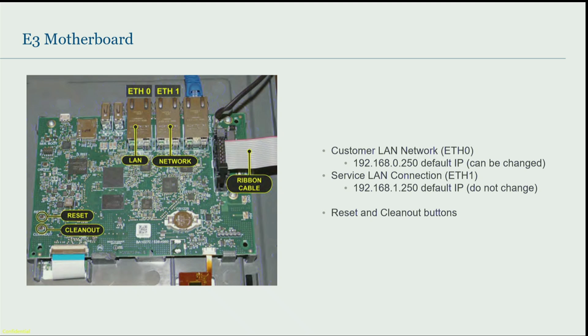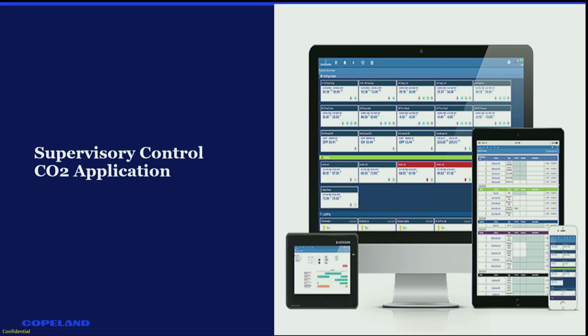So let's talk about communication protocols for CO2 specific devices. When we talk about the CO2 system and how we want to manage it, I'll show you a quick little layout. In the controller with the CO2 applications, you've got an E3 which is managing my compressors and my condenser and the site supervisor as well. You've got the high pressure controller which is controlling the high pressure and the bypass valve. And then you've got your case controllers controlling your low temp and medium temp evaporator. So just knowing how that system lays out, how each part of the system controls its own part, helps you get into the other pieces.